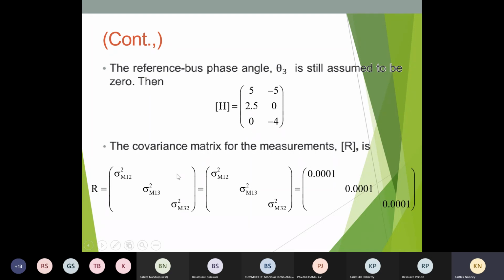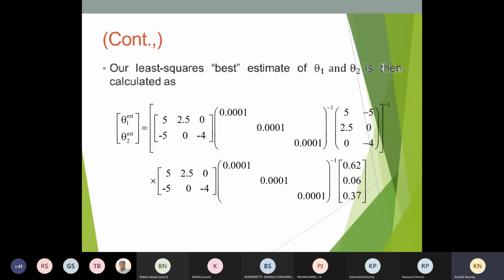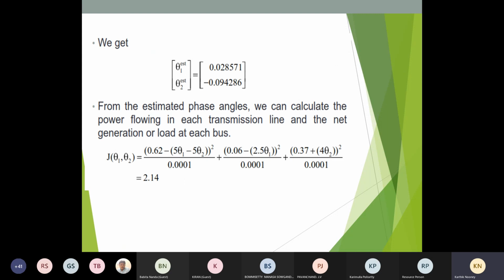Then the covariance matrix is given by sigma square M12, M13, M32. Only 3 buses are considered here, covariance, and that variance is given as 0.0001, 0.0001 and 0.0001. In our weighted least square approximate method, the formula is given by theta estimate equal to G inverse. What is G? G is H transpose R inverse H, whole inverse, again H multiplied by R inverse into these measurements 0.62, 0.06 and 0.37. So if I multiply all these things, you will get the value of theta 1 estimate and theta 2 estimate, calculated as 0.028 and minus 0.094.